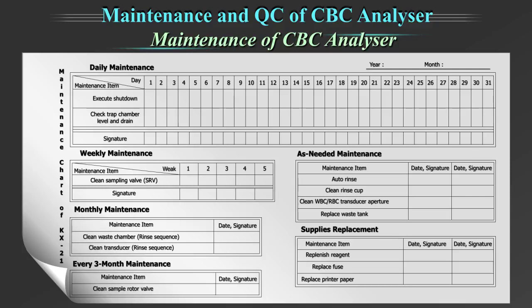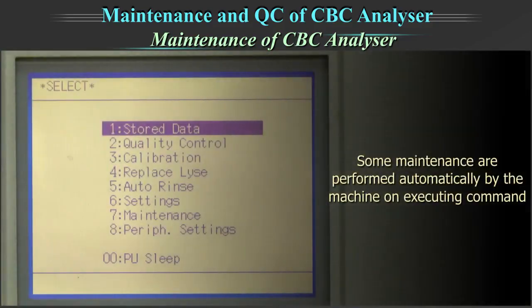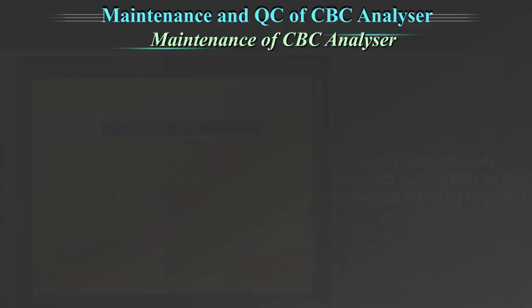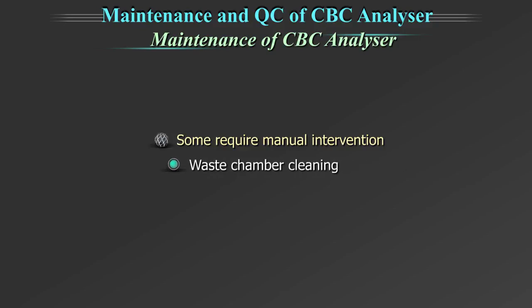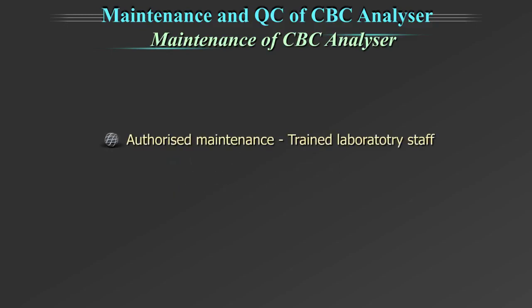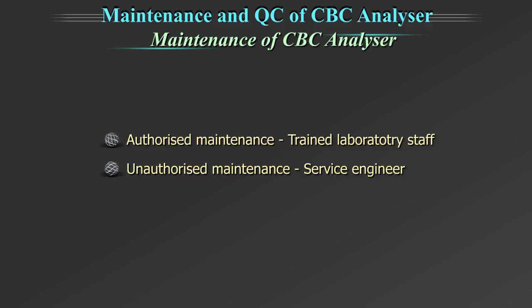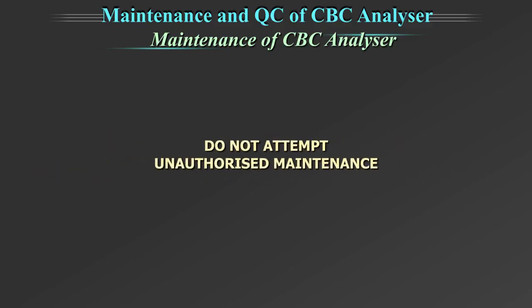Here, the important weekly maintenance includes cleaning of sample rotor valve tray. Some maintenance are performed automatically by the machine on executing commands like auto rinse, whereas some require manual intervention like waste chamber cleaning and transducer cleaning. Some maintenance are authorized for trained laboratory staff, while some are unauthorized maintenance which are done by the service engineer of the company. Please note, do not attempt unauthorized maintenance.